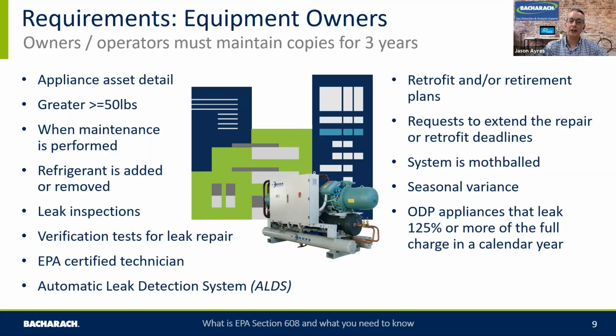Any seasonal variation, so you may be adding or removing refrigerant at certain times of the year for the in-train charge of the system to help its operation. Again, that needs to be documented and captured as well. So you'll see there is a lot of information that needs to be captured and available to the EPA for a minimum of 3 years. All that information I've just touched on is not required to be issued on an annual basis. It more has to be available if the EPA auditor turns up to your site and asks for your records. So bear that in mind when you're looking at your particular enterprise or particular site or assets.